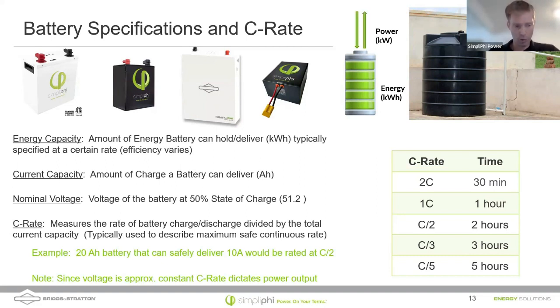Lithium batteries are a lot more efficient than lead acid batteries. And the discharge rate that is typically used is a C/5 discharge rate. So what does that mean? It basically means that the charge within the battery is discharged over a 5-hour period. So if you're discharging one of our Amplify or Phi batteries over a 5-hour period under standard temperature conditions, you're going to get about 3.8 kilowatt hours of energy out of that battery bank.